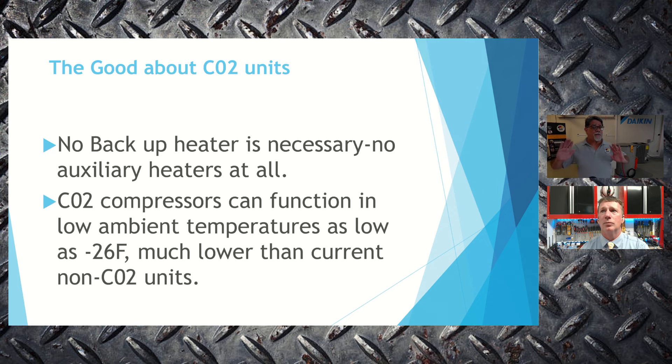Between minus 26°F and 114°F, the unit works fine. Below minus 26°F, it will take a little longer to heat the tank and the temperature will come down a bit, but it's still working — just not at ideal optimal conditions. One person on social media reported a system lockdown and lockout at very low ambient conditions, but you'd have to get below minus 26°F before encountering that scenario. Very well insulated lines are recommended in northern climates.